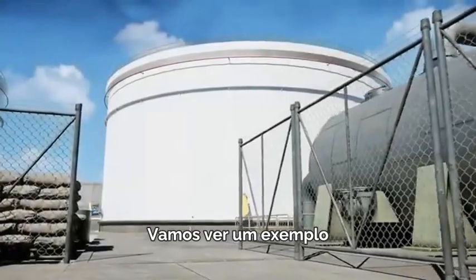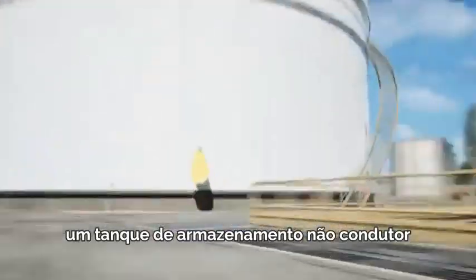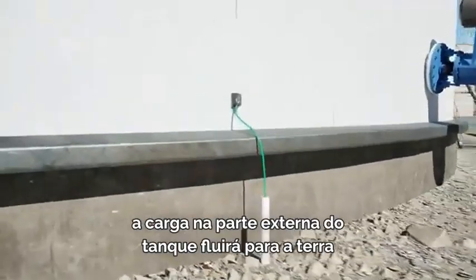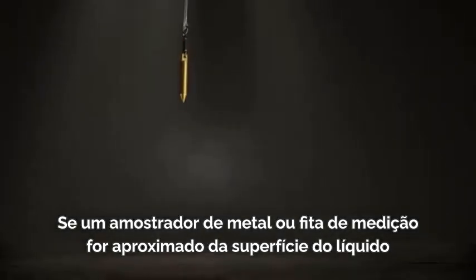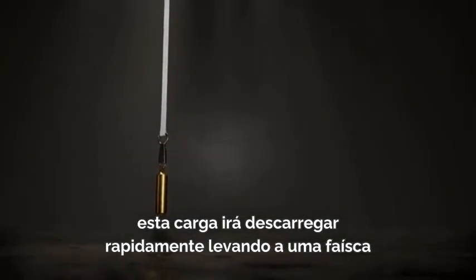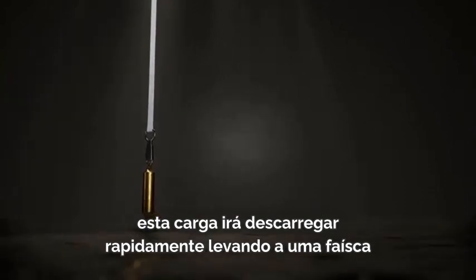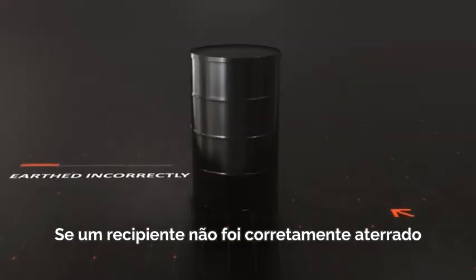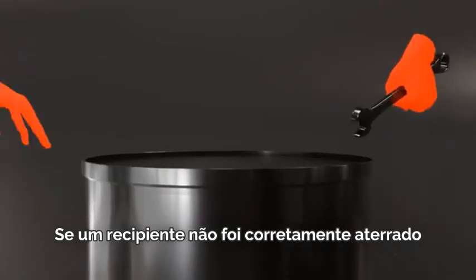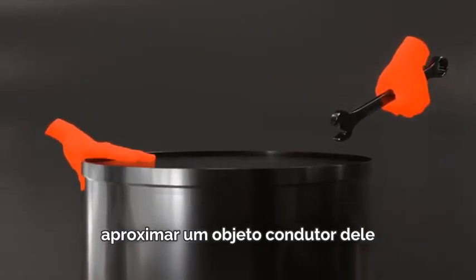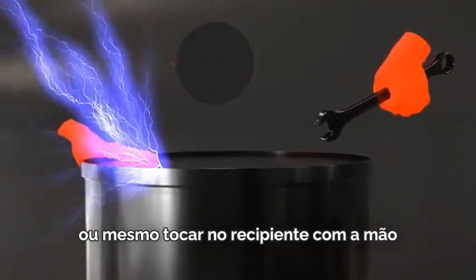Let's look at an example, in this case, a conductive storage tank. If properly earthed, the charge on the outside of the tank will flow to earth. But a charge can exist in the tank for some considerable time following pumping or mixing. If a metal sampler or dip tape is brought close to the liquid surface, this charge will rapidly discharge, leading to a spark. If a container hasn't been correctly earthed, bringing a conductive object close to it, such as a spanner, or even touching the container with your hand, could cause a spark.